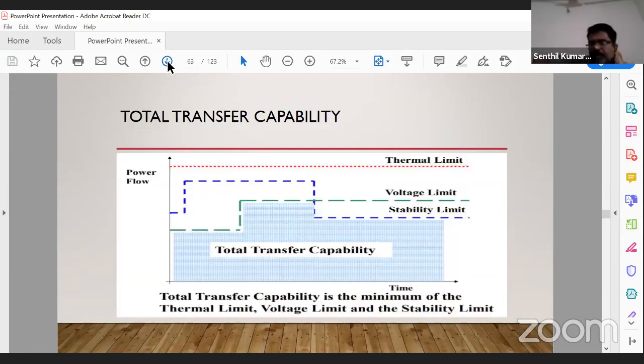In this perspective, we have to manage and construct transmission lines. What conditions govern total transfer capability? Thermal limit, voltage limit, and stability limit - these three limits are followed. As per the transmission planning criteria, stability limit is the main one, voltage limit is second, and thermal limit is third.